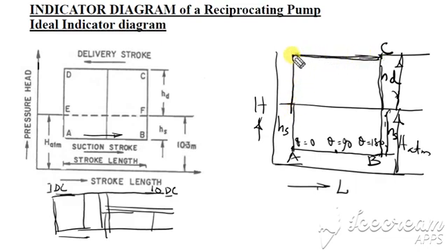Discharge is complete at this point. At the middle of the delivery stroke, theta is equal to again 90. Important thing to notice, on account of negative sign you can write theta is equal to zero in this case here and theta is equal to 180 for delivery stroke here, otherwise it is 180 to 360 for the crank revolution. This is the delivery stroke and the lower one is the pressure variation during the suction stroke, and in between our main reference is atmospheric pressure.